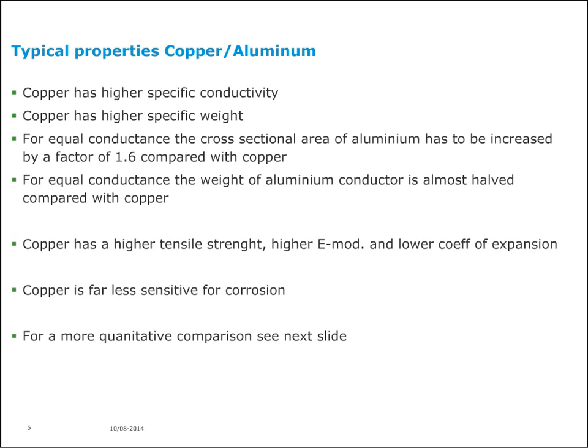Copper has a higher tensile strength, higher elasticity modulus, and a lower coefficient of expansion. Copper is far less sensitive to corrosion. This is a very important difference: aluminum corrodes quite rapidly, while copper does not.